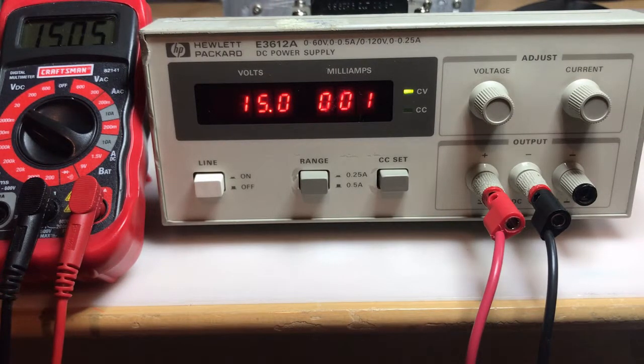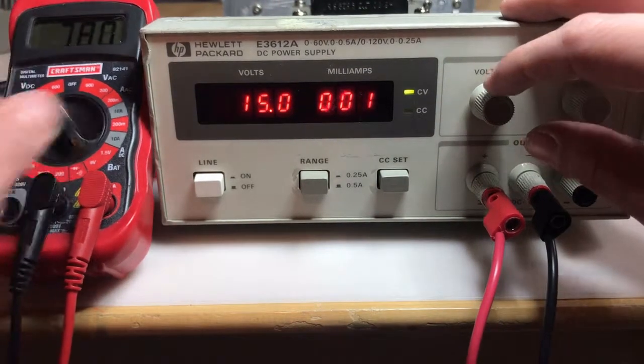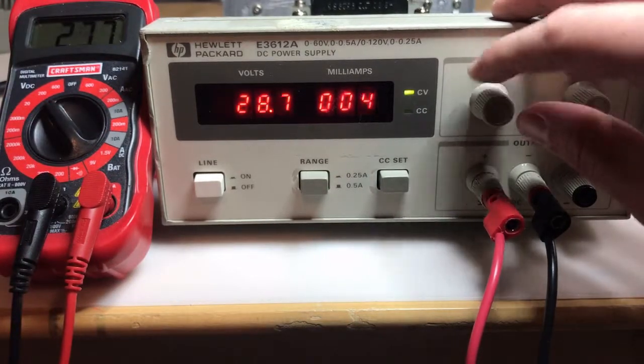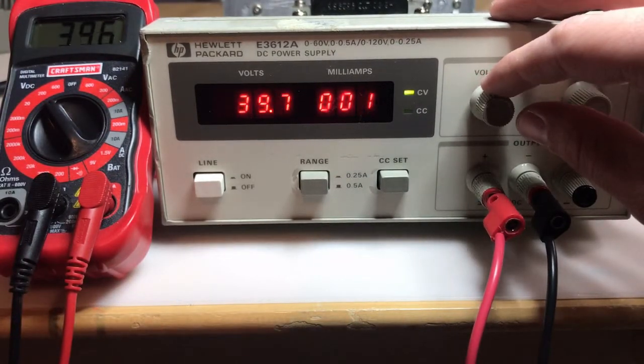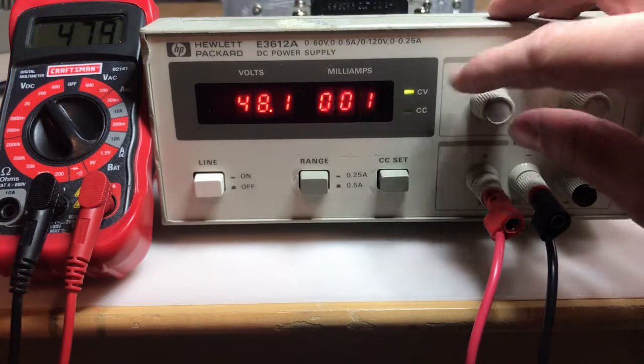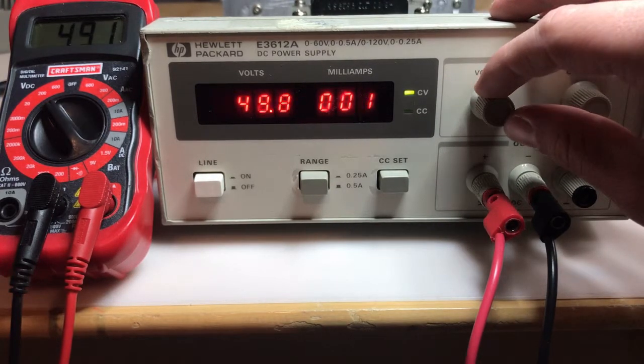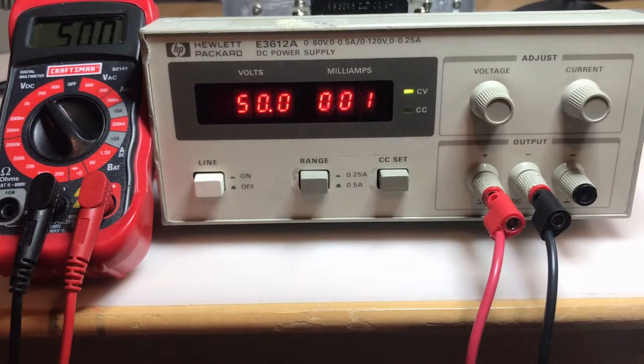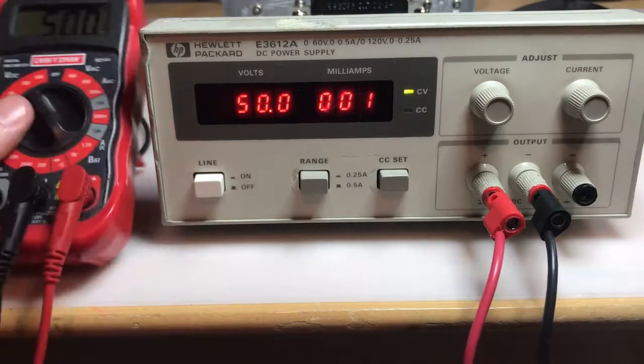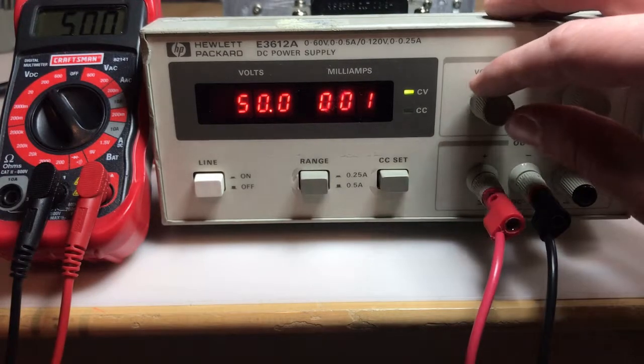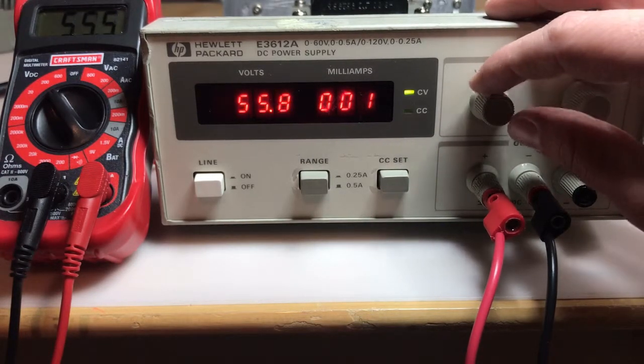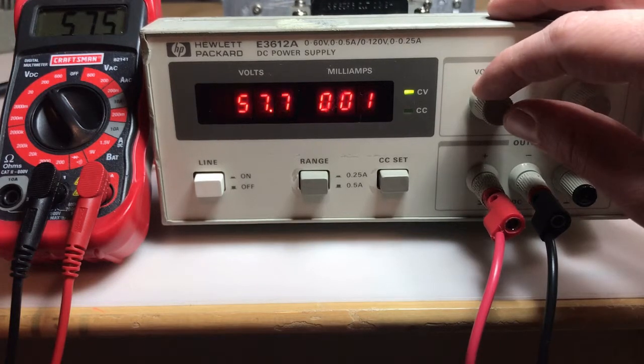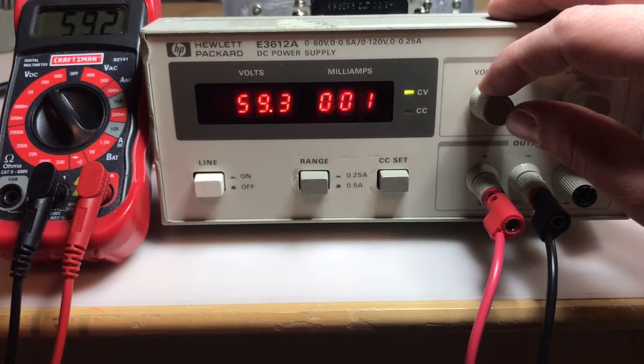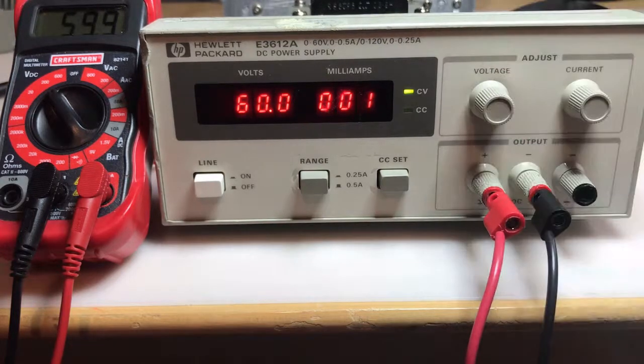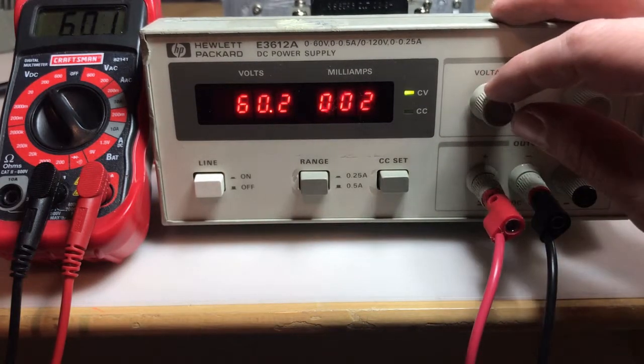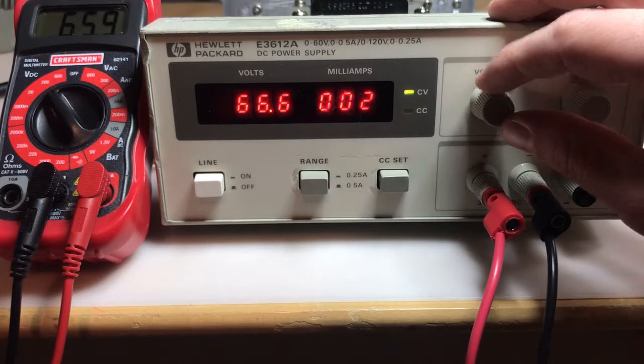0.04. Good. And let's go up to 50. See if we can get up that high. Still not reading much on the current. 1 to 2 milliamps, not a big deal. Okay, 50 on the dot. Okay, that's great. Let's see if it'll go to its full range at the 0.5 amp set point of 60 volts. It gets there, and I'm reading 59.99. Let's see if it goes past it. It does.